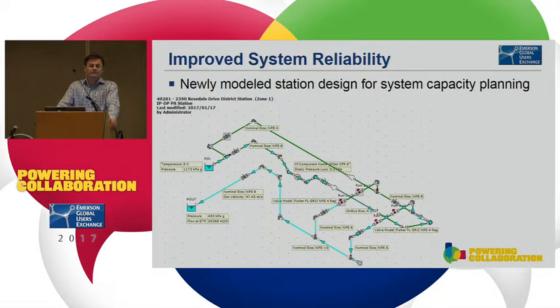So how do we review station capacity? We have custom-built software developed specifically for FortisBC about 3 years ago, which is now widely available for other utility companies looking to use it. We create a model of the piping and each piece of equipment used in the design, and also create a regulator database. In this case, we created one for Fisher FL SR2 regulators for both runs, and we calculate the station capacity.